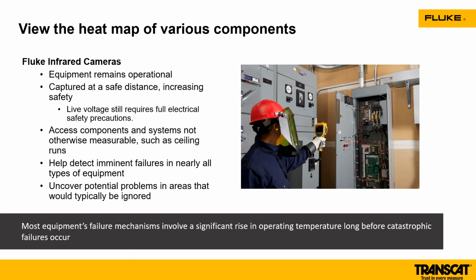Now, another tool that's really critical and keeps you safely out of that zone is an infrared camera. These items are heating up, and with the heat comes a fault. Going in and maintaining, and being able to pre-check with a thermal imager is huge. We can safely do this from a distance. Again, it's increasing that safety. We can look at live voltage and live situations on panels, on motors, and again, document and see what's happening. Because the more we document it, the more we see it, the potential of catching that before it faults is going to be critical. So again, another safety play on that.